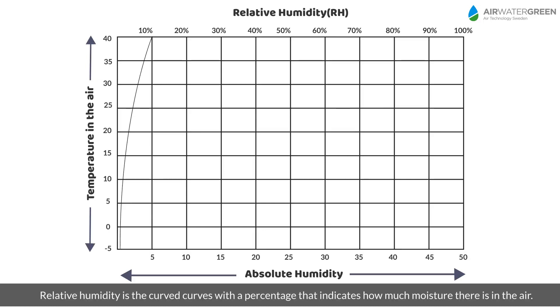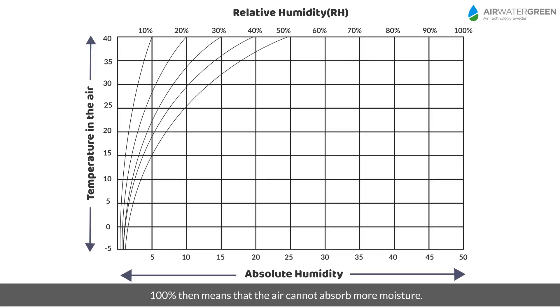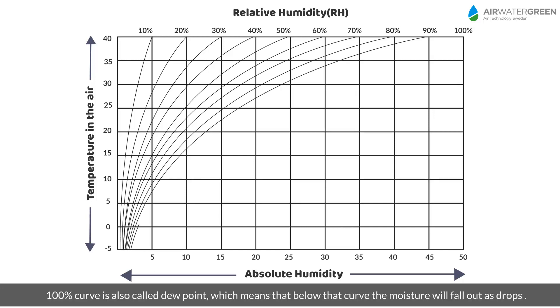Relative humidity is shown as curved lines with a percentage that indicates how much moisture there is in the air. 100% means that the air cannot absorb more moisture. The 100% curve is also called the dew point, which means that along that curve the moisture will fall out as drops.